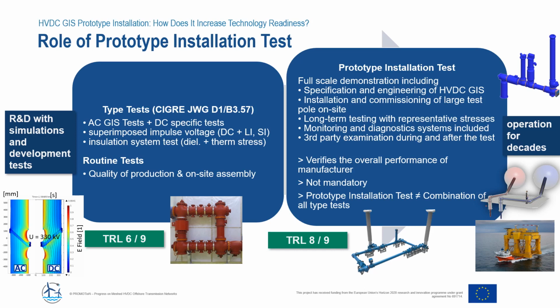And a successful prototype installation test would verify the overall performance of a manufacturer to develop and produce and commission an HVDC GIS product. It is not a mandatory test, and it is also not a combination of all the type tests.